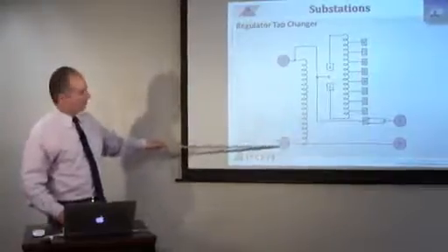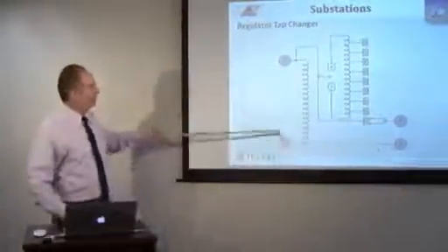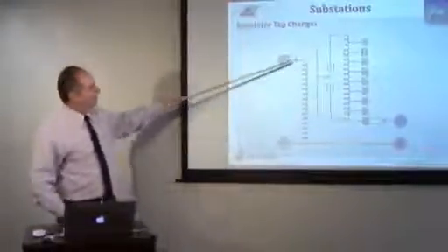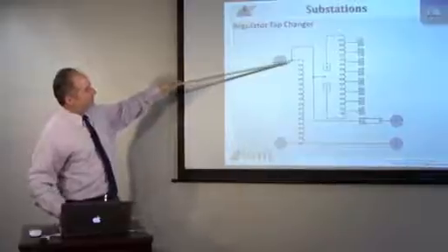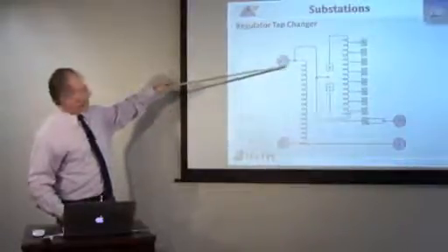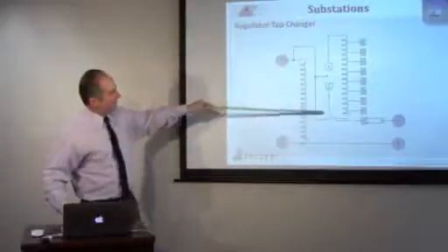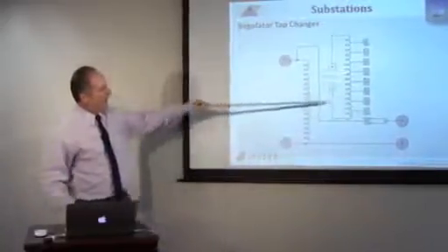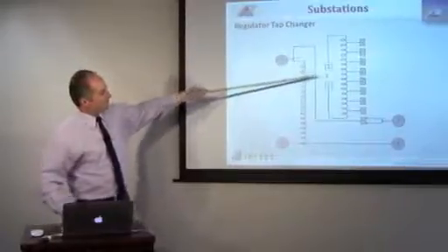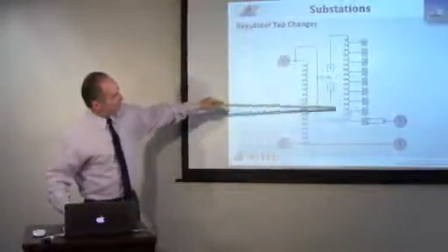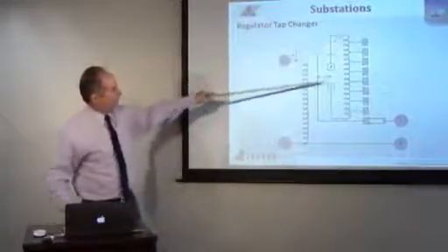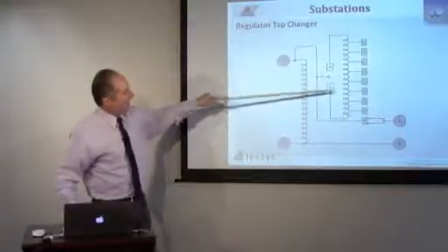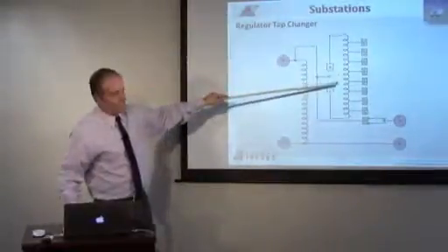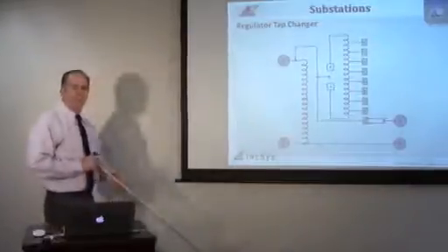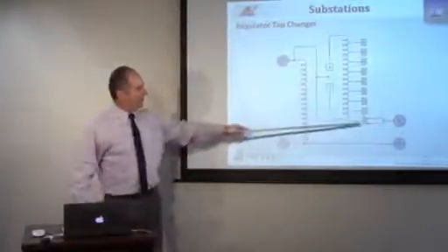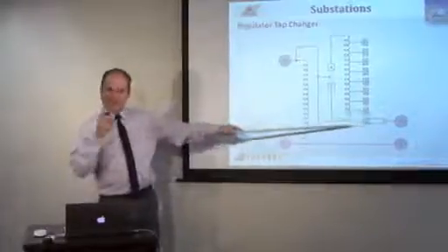You have a common bushing, which is typically the neutral. You have a source and a load. Okay? So when you put power from the transformer here, we now either increase the turns ratio or decrease, depending on how this is set up. If this switch here went to the A position, then you're adding turns and you're raising the voltage. If this were in the B, then the magnetic fields cancel out instead of add, and you're actually lowering the voltage.